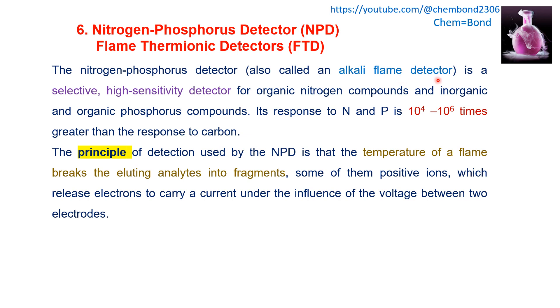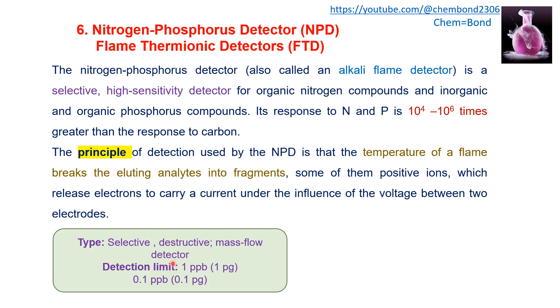The nitrogen phosphorus detector (NPD), also known as the alkali flame detector, is a selective, highly sensitive detector for organic nitrogen compounds and inorganic and organic phosphorus compounds. It responds to nitrogen and phosphorus at 10^4 to 10^6 times greater than its response to carbon. The principle of NPD is that the temperature of the flame breaks the eluting element into fragments, some into positive ions which release electrons to carry a current under the influence of voltage between two electrodes. Temperature breaks down the eluting element into fragments, producing positive ions and electrons, and current is produced when these positive ions move towards the collector electrode.